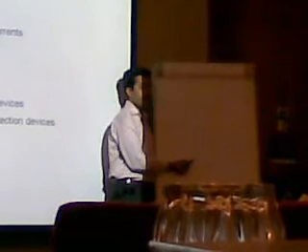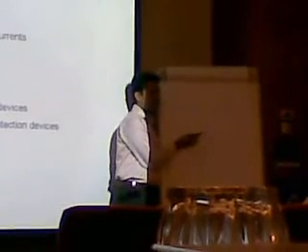Selectivity of the breaker. Now, if there is a fault here, assume that this is the main switchboard. In the main switchboard we have main breakers here, maybe a number of breakers or more. When there is a fault in the switchboard, which has to trip? The first trip. This has to trip. Obviously, if this breaker trips, we will lose the supply for the complete network.